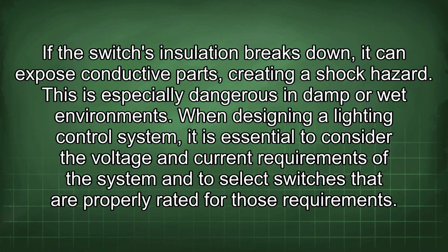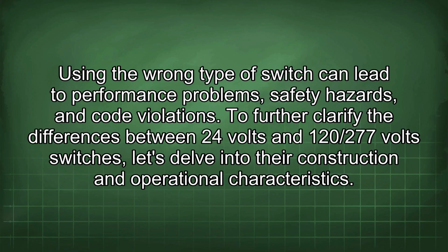When designing a lighting control system, it is essential to consider the voltage and current requirements of the system and to select switches that are properly rated for those requirements. Using the wrong type of switch can lead to performance problems, safety hazards, and code violations. To further clarify the differences between 24 volts and 120/277 volt switches, let's delve into their construction and operational characteristics.